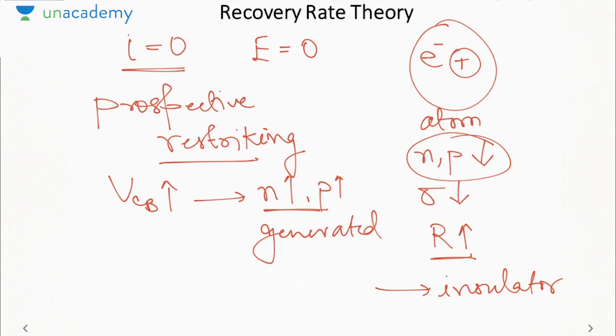Recovery rate refers to the rate at which ions recombine and the material recovers from its conducting state to its insulating state. If recovery rate is higher than the rate of restriking voltage, the arc will extinct. If the rate of restriking voltage is higher, the arc will exist for another half cycle, and at the end of that half cycle, we apply the same theory again to determine whether the arc extincts. So we operate based on every half cycle.